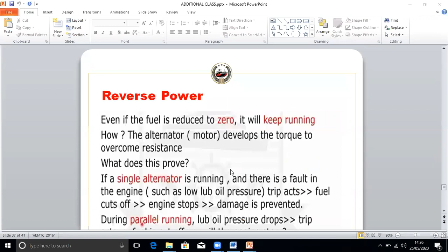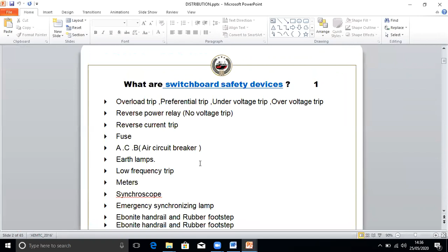So let's go to today's topic, and this is the distribution system. This chapter is 2.3.9 distribution. The topics to be covered: we will see switchboard safeties, what the switchboard safeties are, and when you do a switchboard survey, what parameters are to be checked. Then you will see the main switchboard: what things to see, like a tie breaker and its function, the layout of a main switchboard, what a bus bar is, and the various types of breakers. Then you will see earth monitors, how an earth monitor works, and what the IR values are.